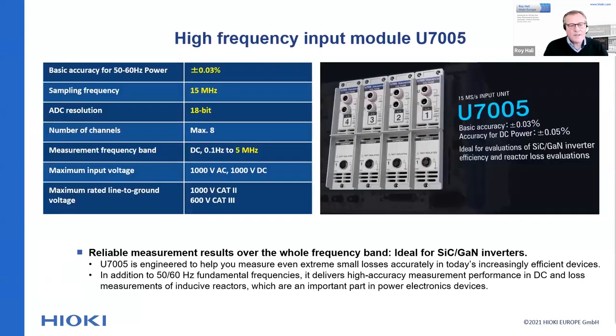The other unit, the U7005 high accuracy input unit, with its base accuracy of 0.03 at 50 to 60 Hertz and a sampling frequency of 15 megasamples per second, and a power bandwidth of 5 megahertz, is developed for the evaluation of SiC and GaN-based products and gives a better result at low power factor measurements, like reactor measurements of inverters drives that we mentioned earlier in the presentation.